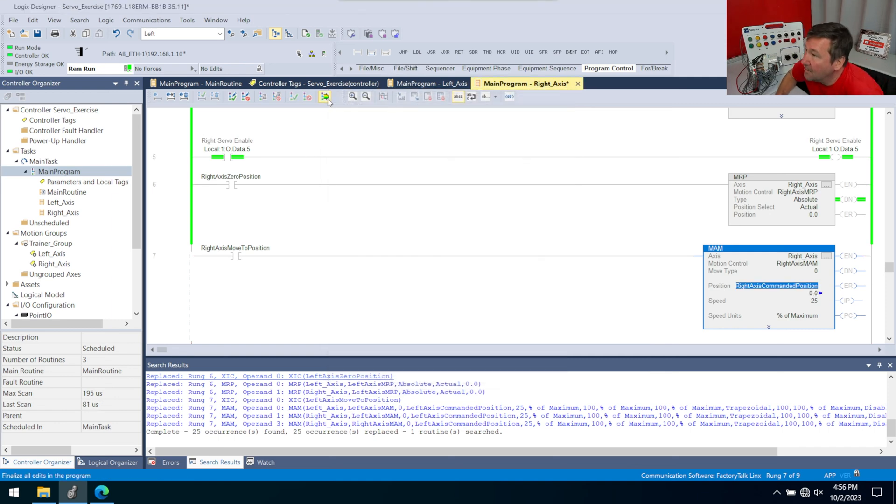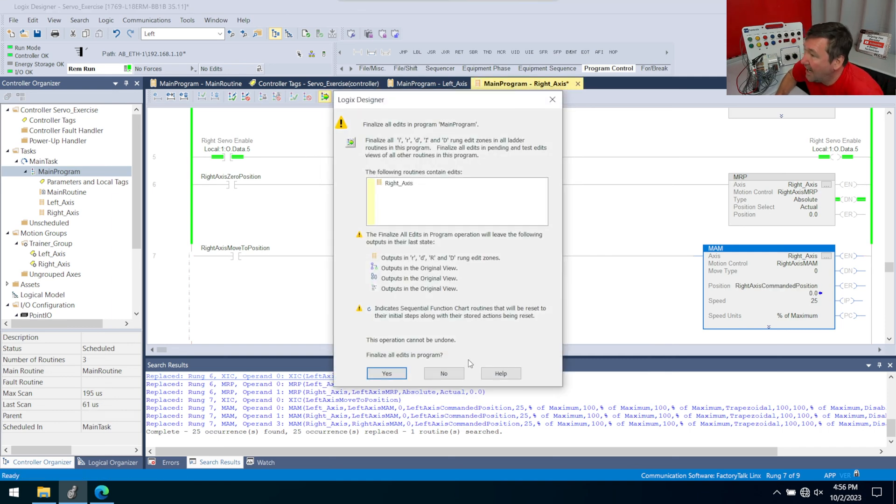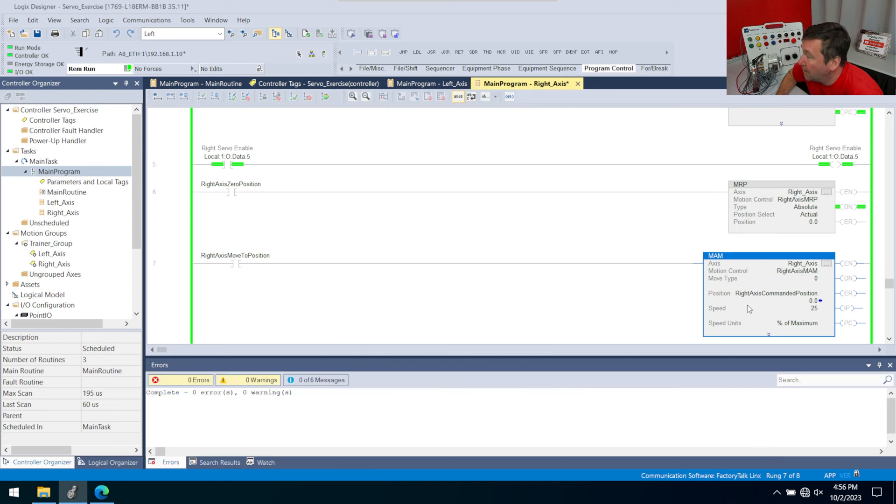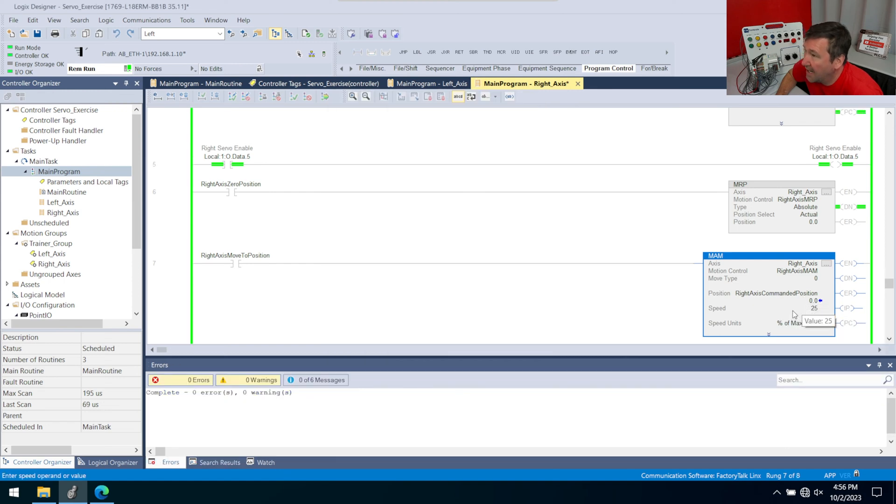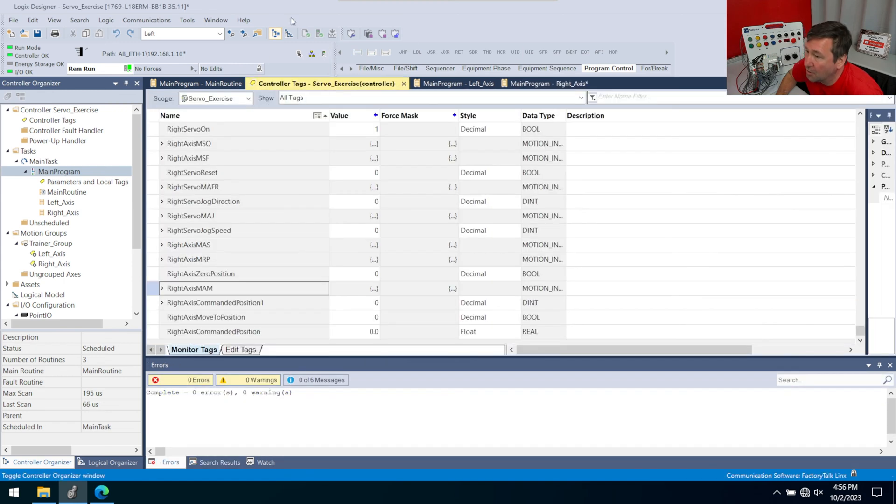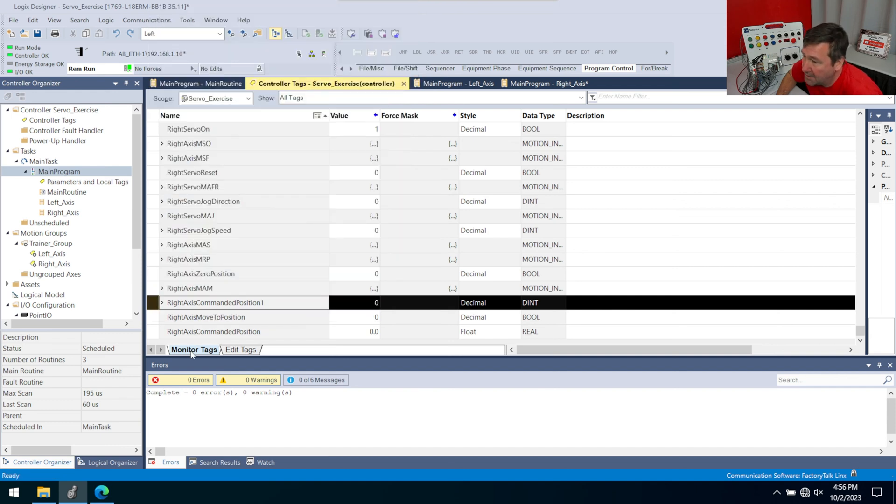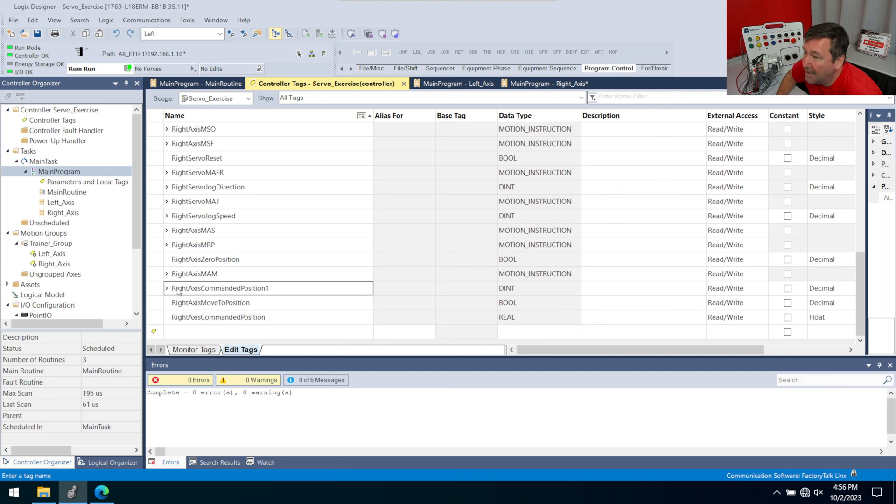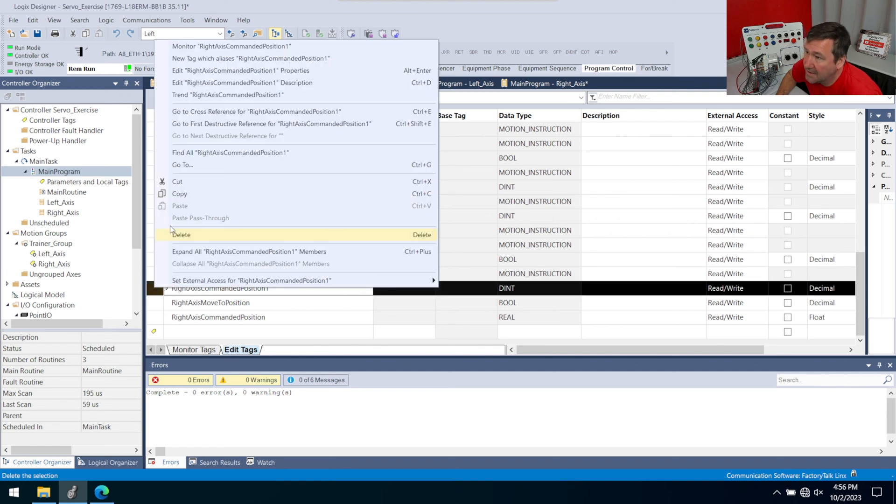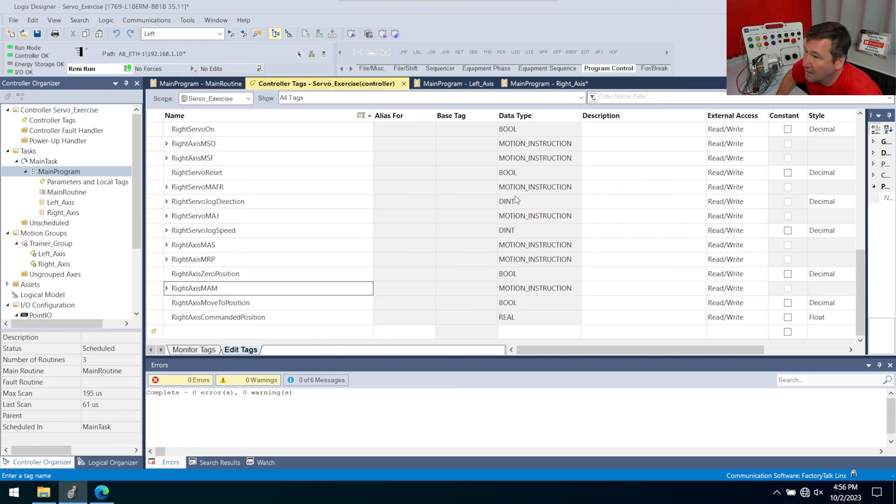Now if it really bugs you that we have that junk tag in there now, you can go over to your controller tags. And we don't talk about this that often anyway. But you think you could right click that tag and simply delete it. But you can't because we have two tabs down here, we have the monitor tags, we have an edit tags, we go over to edit tags. Now we can right click and delete.